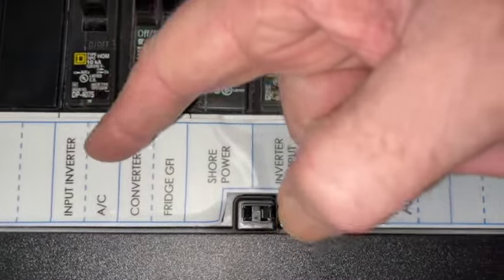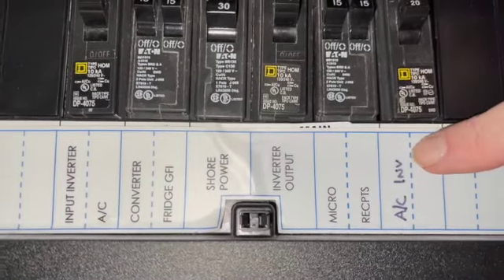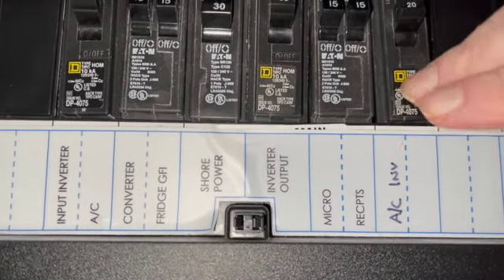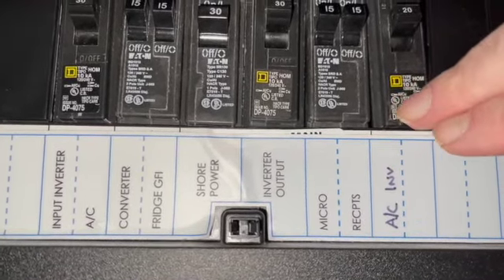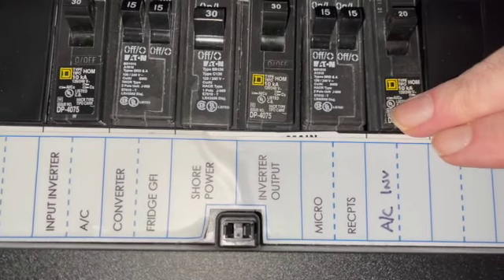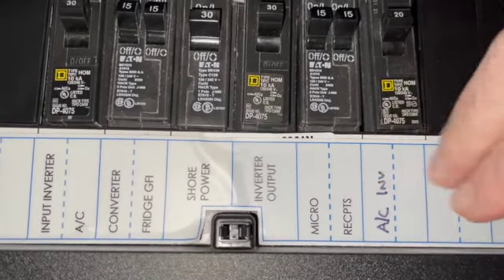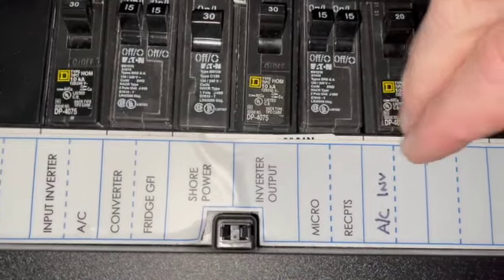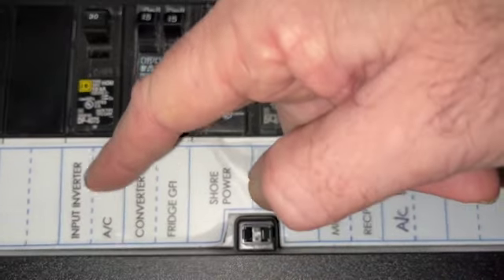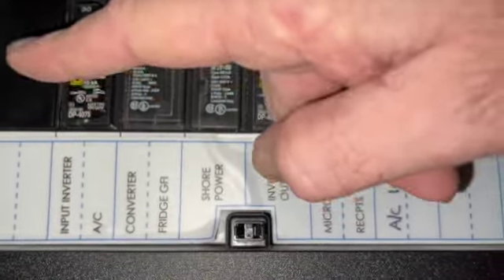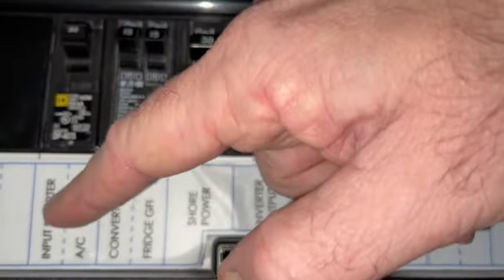But as you may recall from my earlier videos, I moved the air conditioner over to the inverter side. See here, the air conditioner is running off of this 20 amp circuit breaker right here on the output of the inverter only. So I didn't really need this any longer. So I replaced the dual breaker with a single 30 amp breaker just to run the input of the inverter.